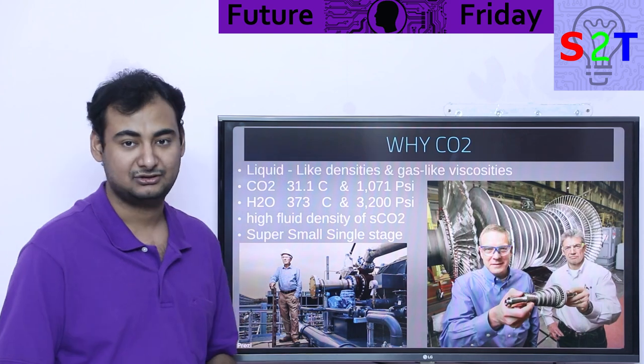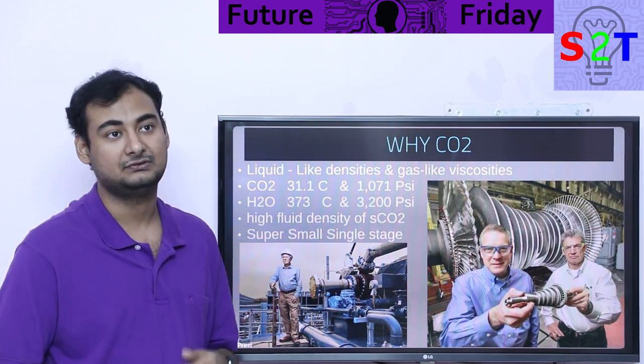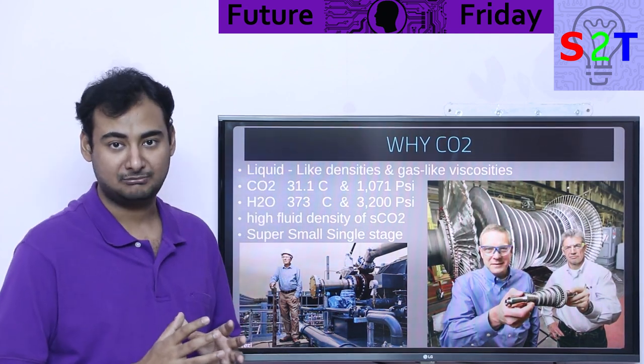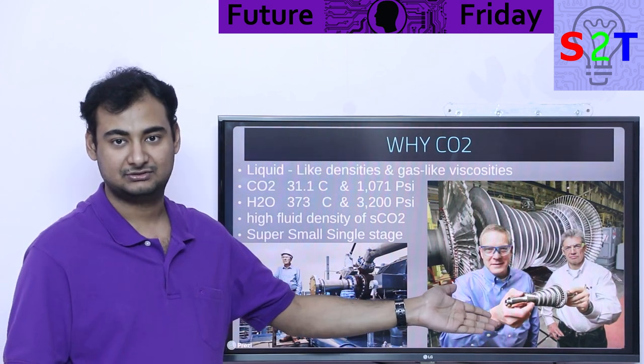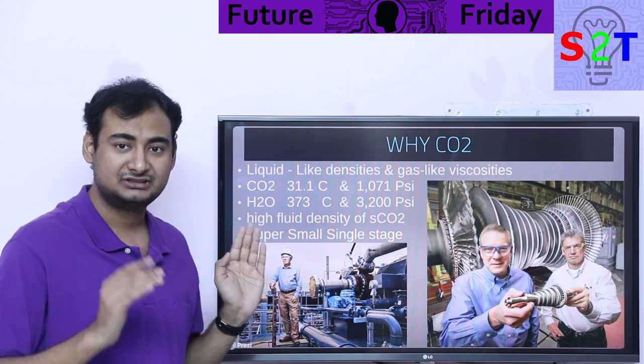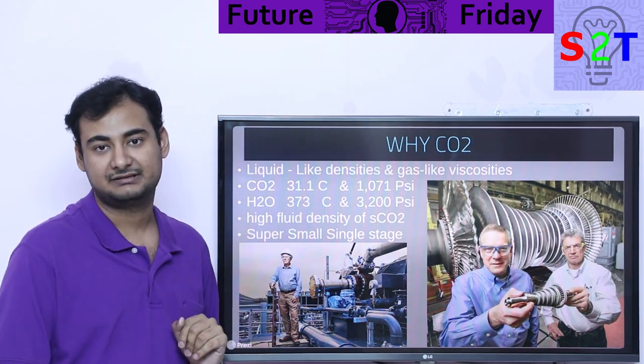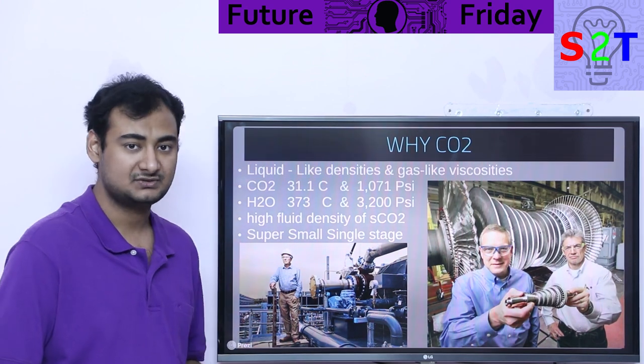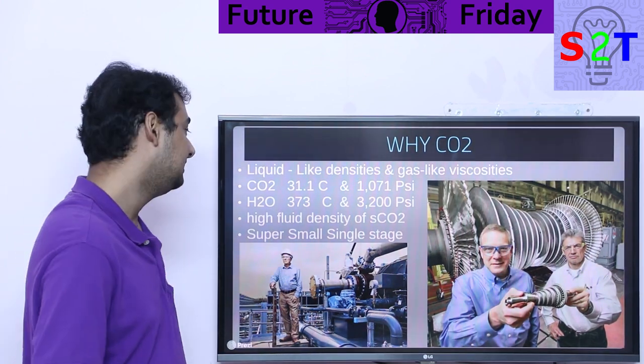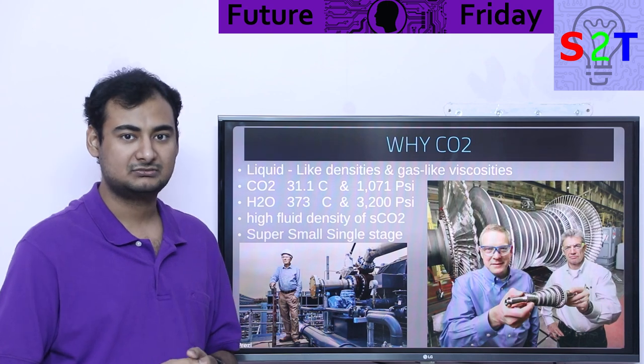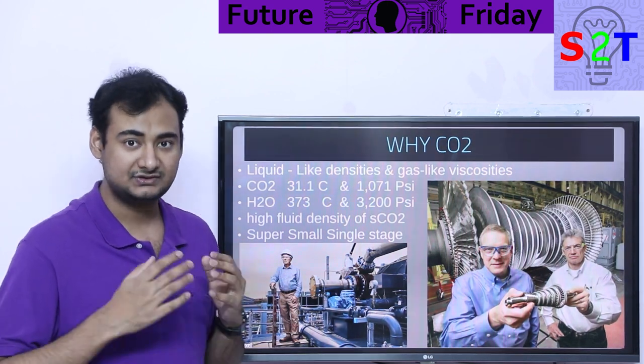That is why everyone is looking into this. There are other gases that have been considered — mercury, helium — but if you want small and compact, carbon dioxide is your best option. The minimum conditions for supercriticality are around 31°C at 1,071 psi. That's not negligible — 1,000 psi is something serious — but steam power plants work at much higher psi. New coal power plants are focusing on supercritical steam to improve efficiency.